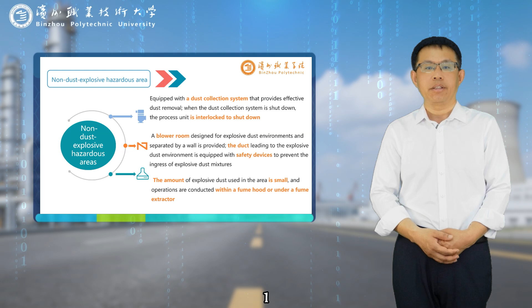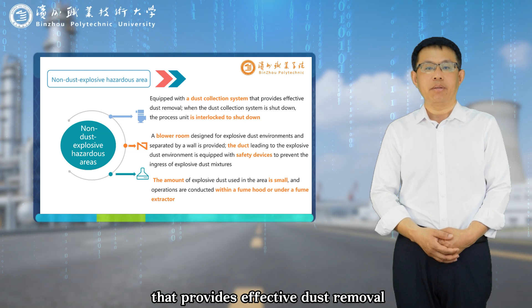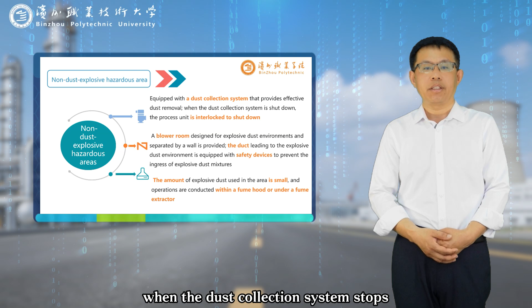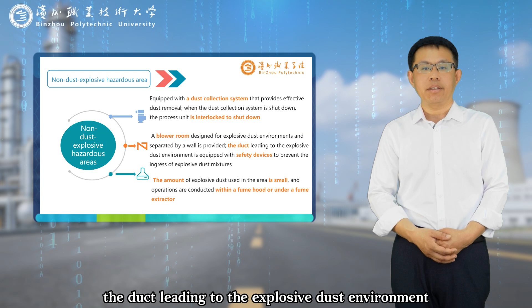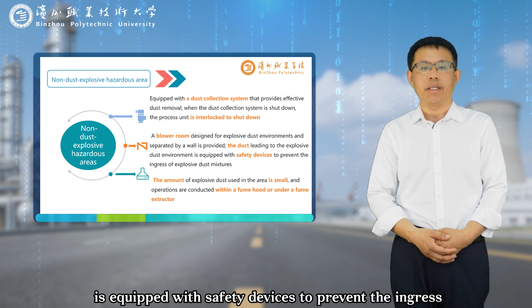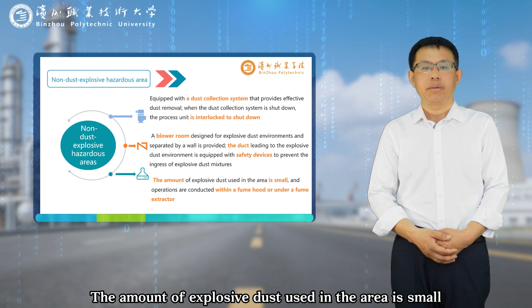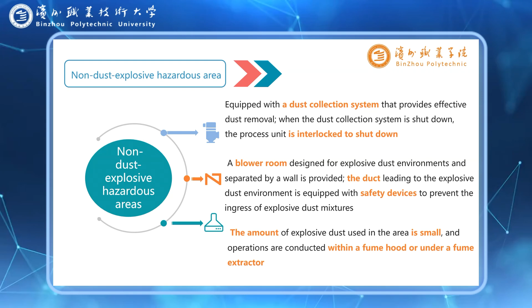First, the area is equipped with a dust collection system that provides effective dust removal, and the process unit is capable of interlock shutdown when the dust collection system stops. Second, a blower room serving the explosive dust environment is provided and separated by a wall. The duct leading to the explosive dust environment is equipped with safety devices to prevent the ingress of explosive dust mixtures. Third, the amount of explosive dust used in the area is small, and operations are conducted within a fume hood or under a hood.